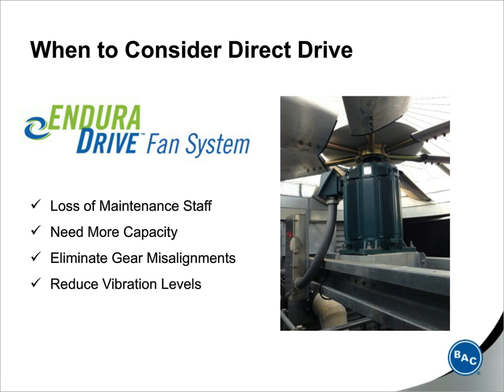If your tower falls short of required performance, let's say that there have been new heat loads added to the building, more people, more equipment over time, the direct drive fan system can actually add enough thermal performance to ensure that the building can meet its required cooling capacity.